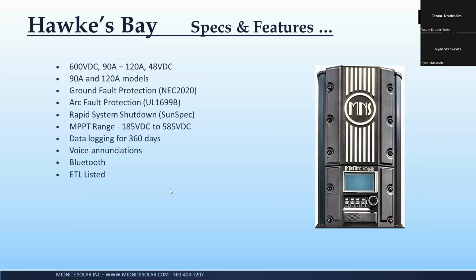I've got a system I'm working on now with a customer that has 24 600 volt 60 amp charge controllers by somebody else who I won't name. The white ones with the black fins on them, and the BMS opened and they all blew up. And when he contacted the company to talk about that, they said that wasn't a warrantable situation because the device is not intended to have the battery disconnected. So he asked us about ours, and I said, absolutely. Every one of our products is intended to have the battery disconnected while it's running at full tilt. It's not going to keep running, but it's not going to hurt the device.